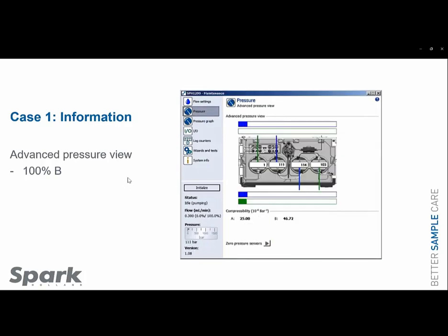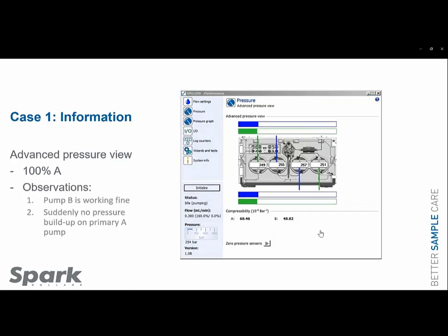We will continue with pumping 100% B and see what's happening. So it's building up pressure. The primary is 6 bar below the secondary. It's refilling correctly. It's also generating a compressibility factor. So pump B is good. Let's see what pump A is doing. So pump A is loading. It is 6 bar below the system pressure, generating compressibility.